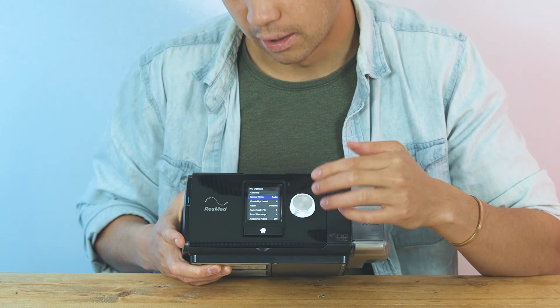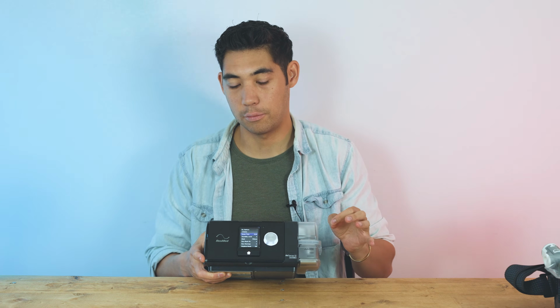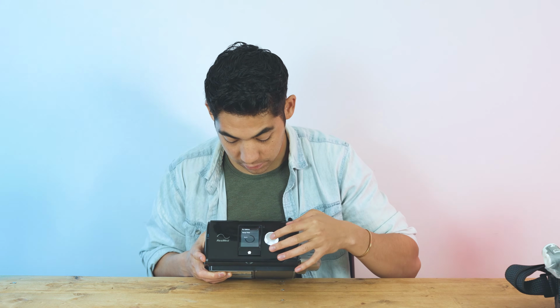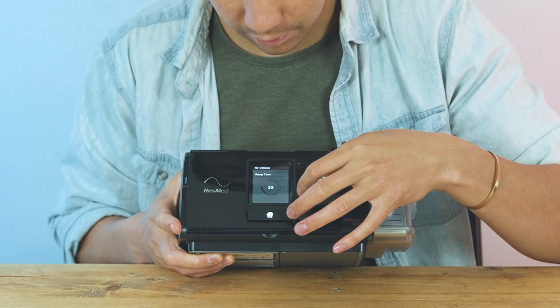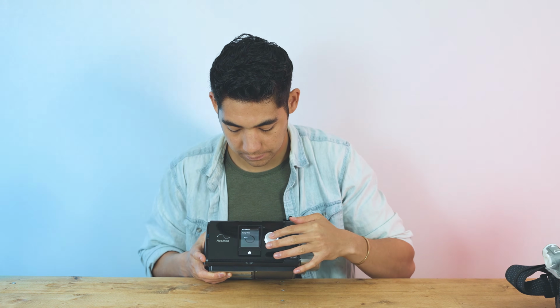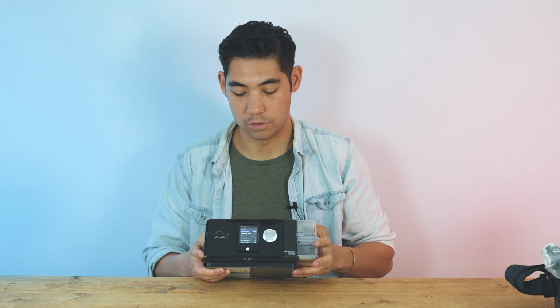So ramp time. The first thing is ramp time. That's how long it takes to get to your prescribed air pressure. So it's going to be a little more comfortable if you start sleeping with a lower air pressure. So that's what the machine can do. You start off with a lower air pressure and you select different ramp times. So how many minutes you want to get to your prescribed higher pressure. Now I'm just gonna keep that at auto. Most people like it at auto.